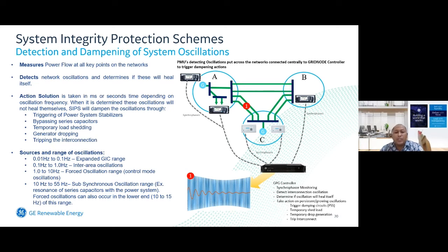So if, for example, the system cannot heal by itself, then action can be taken in milliseconds or seconds, depending on the oscillation frequency. When it is determined that the oscillation will not heal by itself, our SIPS system will dampen the oscillation through a few steps as below. First is triggering of the power system stabilizer, and then bypassing series capacitor, temporary load shedding, generator dropping, and then when all these solutions are not able to heal the oscillation, it can also trip the interconnection to dampen the oscillation that happens in the system.